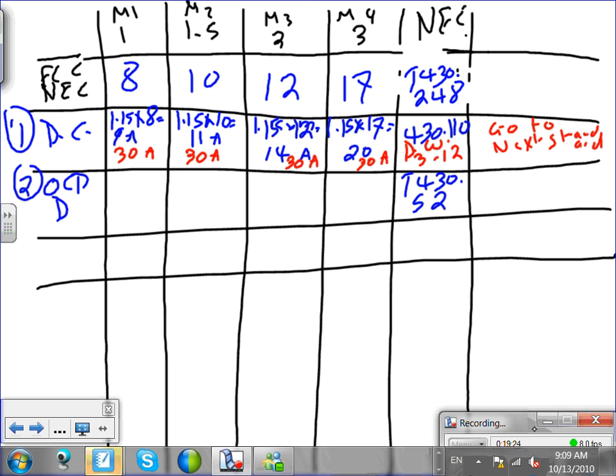Okay, overcurrent protection device, 430.52. Now, can you guys see that there are multiple options there? You're going to ask me, Chad, what type of fuse or circuit breaker do you want? Let's say a dual element time delay fuse. I want to have a dual element time delay fuse. So the type is dual element time delay fuse. Okay, everybody's there?